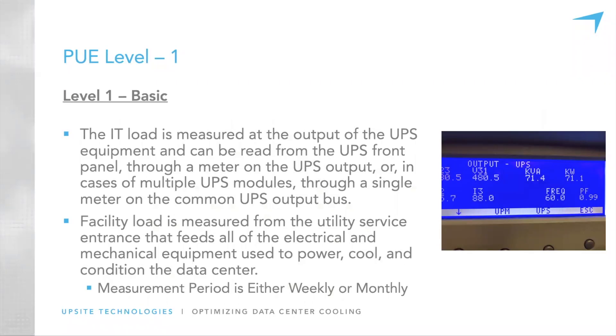There are three levels of measurement with PUE: Level 1, 2, and 3. PUE Level 1 is a basic measurement taken at the output of the UPS system. Most UPS systems have an IO board where you can read the output, and that's where we get our baseline measurement information for a PUE Level 1 reading.